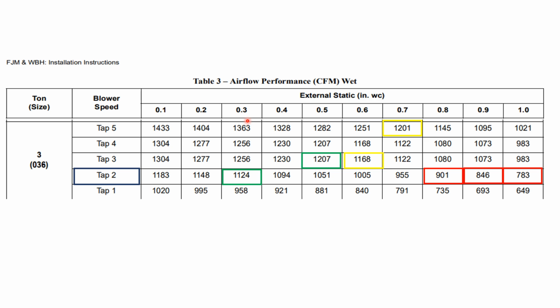So in this particular case, here's what we need to do. We are going to look at the return that we talked about. We're going to set our flex. Let's say we're going to use flex on this one. And we're going to set it at a friction rate of 0.05. And we need 1115, so we're going to set it for 1200, which is 18-inch flex. If we pull our 18-inch flex tight, then we use hard 90s and pull our flex tight, we will carry 1200 CFMs, a little bit more than that, back to our unit.